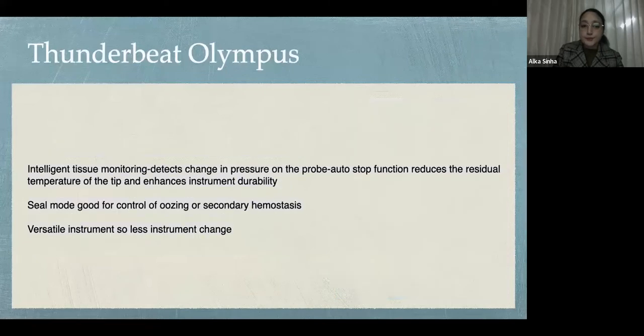It also had an inbuilt intelligent tissue monitoring system which detects the change in pressure on the probe. As the tissue transects, the pressure is relieved, and this leads to an auto stop function. So the delivery of ultrasonic energy is stopped, and this helps in controlling the temperature at the tip of the instrument. It also avoids overheating, so there'll be enhanced instrument durability.